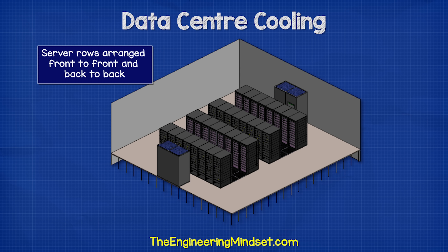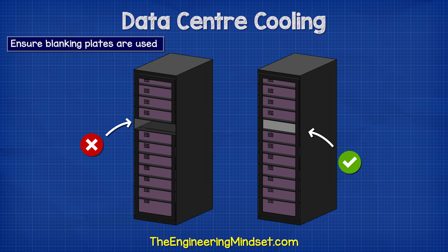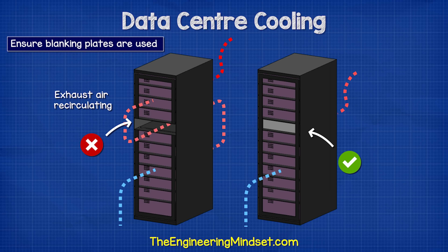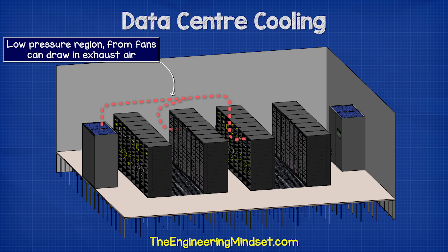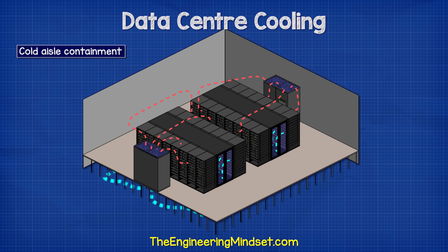Instead, we arrange the rows so that they are facing front to front and back to back. This way, we only provide cold air to the front of the servers and the hot exhaust isn't sucked into another server — creating hot and cold aisles. We need to ensure that empty spaces in the servers are filled with blanking plates to prevent warm exhaust air from recirculating. Additionally, the fans in the server racks cause a negative pressure region at the front of the server, which can draw warm exhaust air down and recirculate it back into the server. For existing data centers, one of the best designs is cold aisle containment, where the cold aisle is covered with a roof and the ends of the aisles are sealed with doors, putting a physical barrier between the aisles to prevent mixing and recirculation.